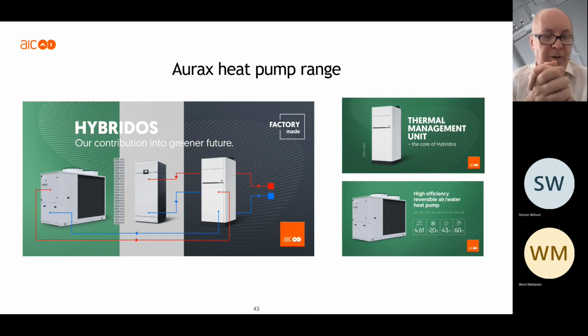And all that technology is used in our hybrid heat pump solution as well, but that's not part of the presentation. I just mention that at the end, but that's something that if you want to talk about, we can talk about another time. Okay, where we've introduced a heat pump, the backup boiler, and a thermal management unit to control both heat sources, which is really designed for existing buildings, where it's been designed on an 80 degree flow, and there's no willingness to change the heat emitters or the pipe work or the fabric of the building. Okay, but they do want to decarbonize.